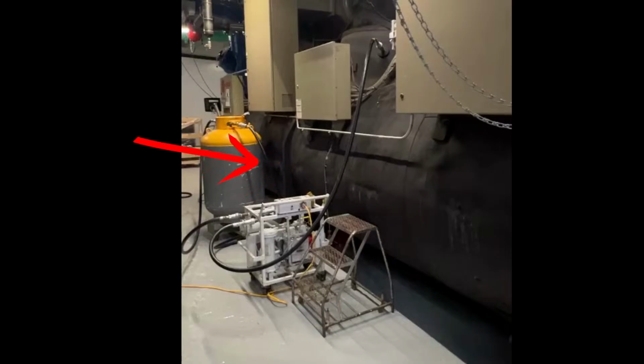At that point, you'll reconfigure everything, and essentially you'll swap the hoses here. Okay, so you can close this liquid valve between the tank and the chiller. I would close it on both ends, and then close all your valves. Swap your hose connections to where the tank vapor is on the output and the chiller vapor up here comes into the input of the recovery machine. Once you swap those around, then you can start doing the vapor pull process to get the rest of the refrigerant out and into your cylinder from there.